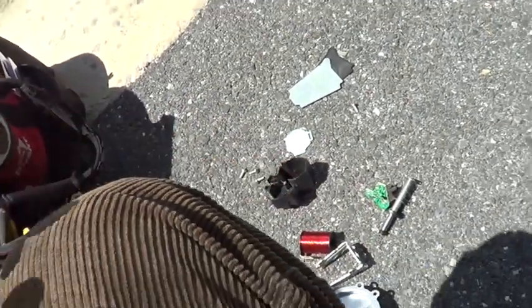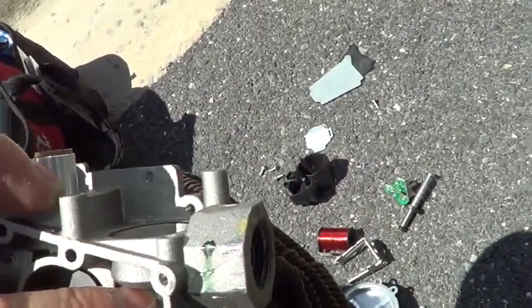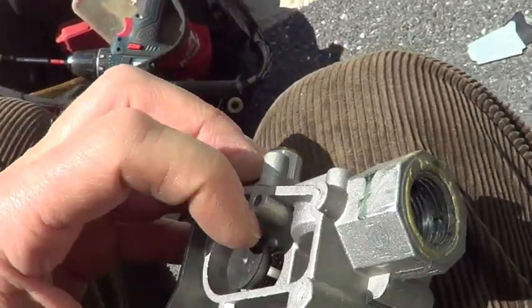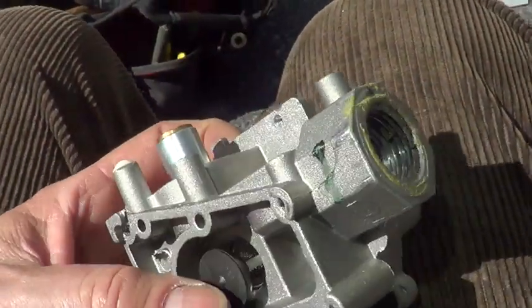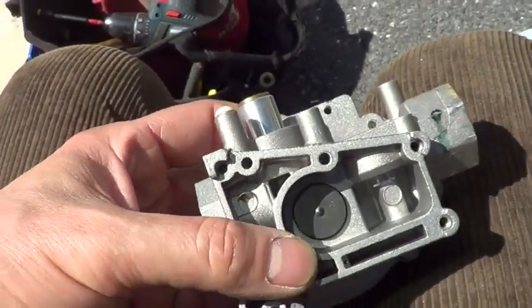If the solenoid fails, it shuts off. If you get trash in one of these plungers, you will get the gas odor, but it's not going to be enough to run this valve wide open. That's the dangerous part.